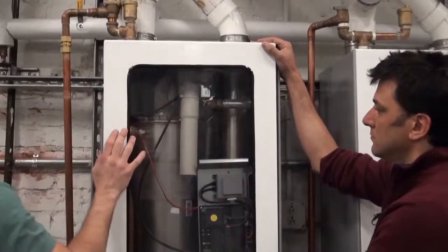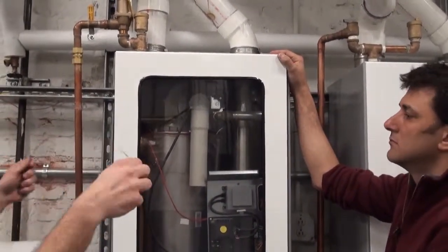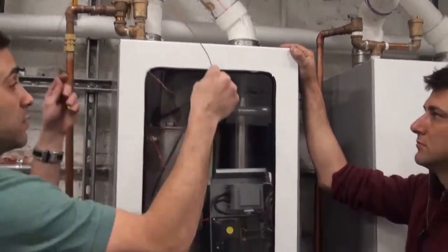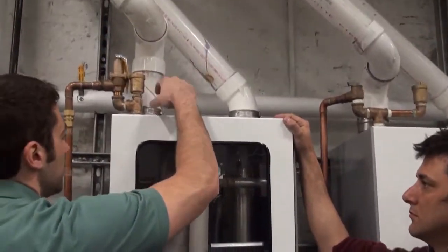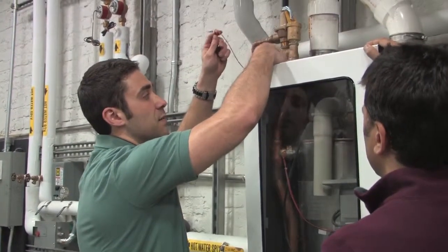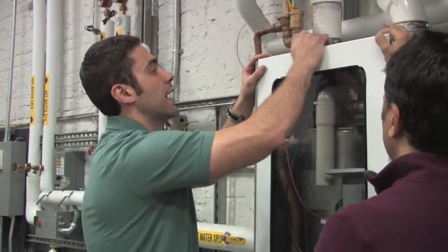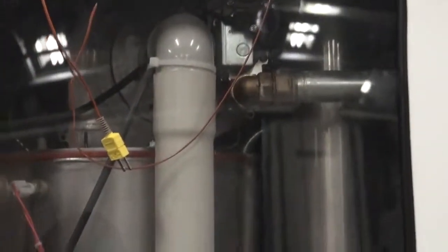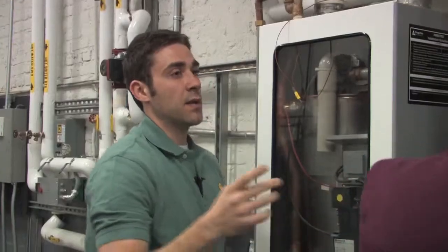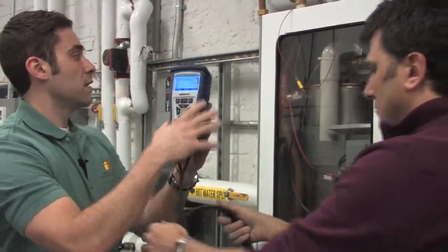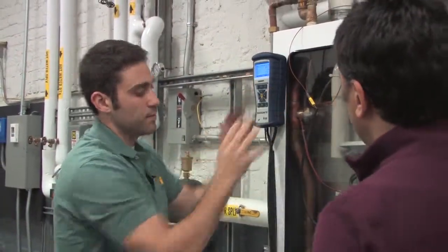But before I put it on, I'm going to run in my temperature probe because I can't use the temperature inside this room. I need to do the outdoor temperature. So I'm going to run this inside here so it samples the air that's coming in from the outdoors and we'll get an accurate reading. All right, so that's set up inside there. I'm going to grab the analyzer. We calibrated that outside, so we're set and ready to go. Put this on here so we can see what we're doing.